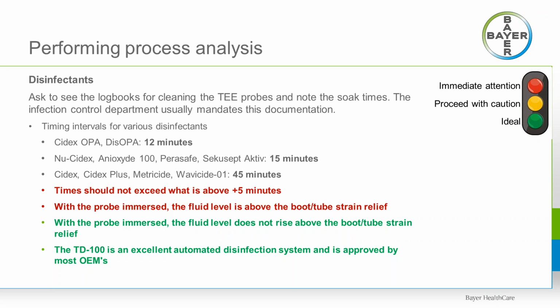OEMs usually state in bold lettering that immersion times need to be strictly monitored, and that the immersion time should never exceed what is recommended. With leakage testing, again, the probe should not be immersed higher than the last number stamped on the insertion tube. More and more options are becoming available to automate the process of disinfection, and the use of something like the TD100 is a best practice, because your times are monitored and logged, as well as the level of the fluid.